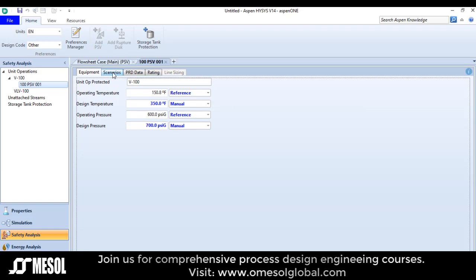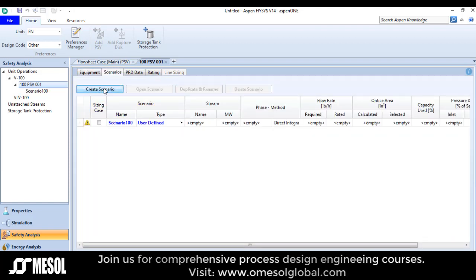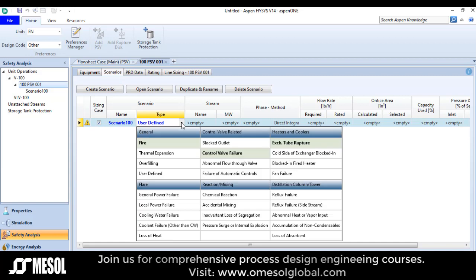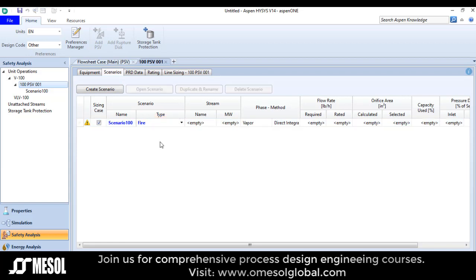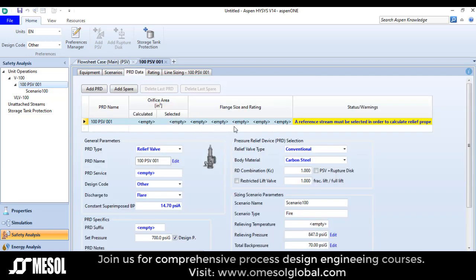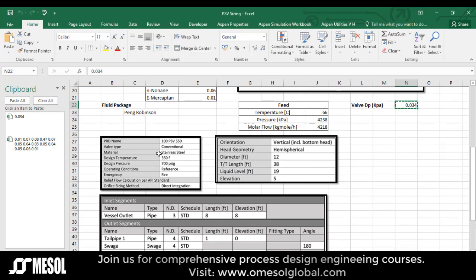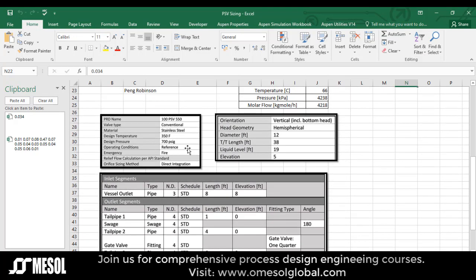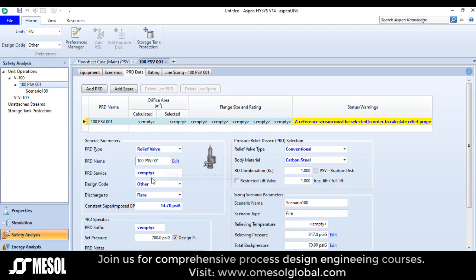Now I move to the scenario tab and click 'Create Scenario'. Check 'sizing case' then pick the fire case. After selecting a fire case, I will go to PRD data and define the relief valve specification. The design code is 'other' for API. Discharge location is flare. The constant superimposed back pressure and the set pressure are also defined.